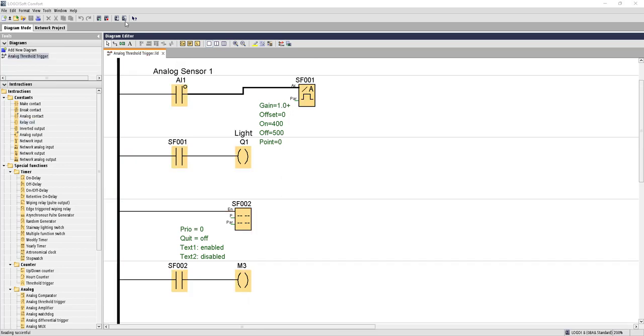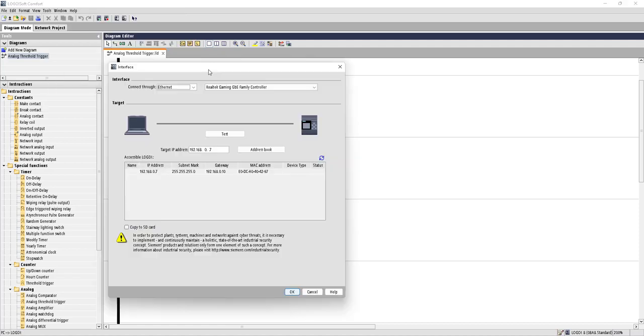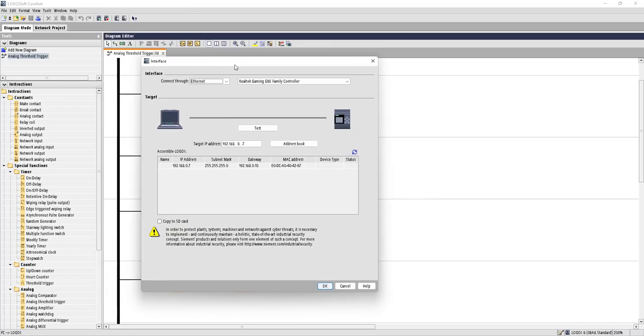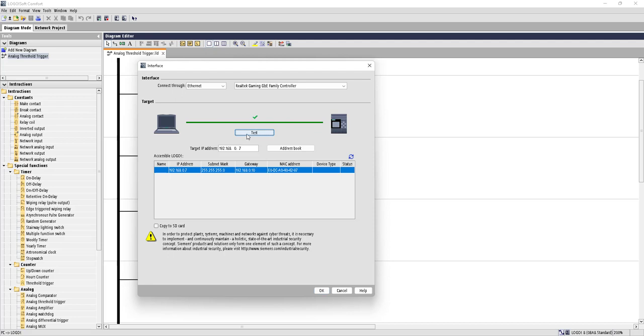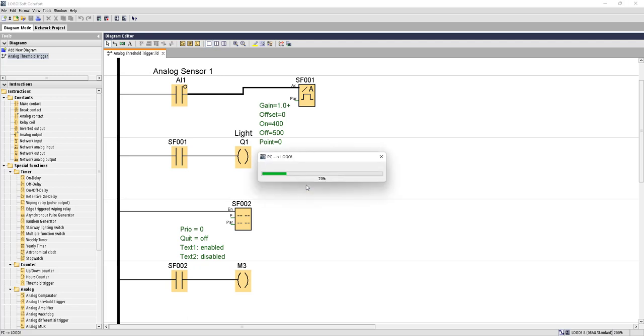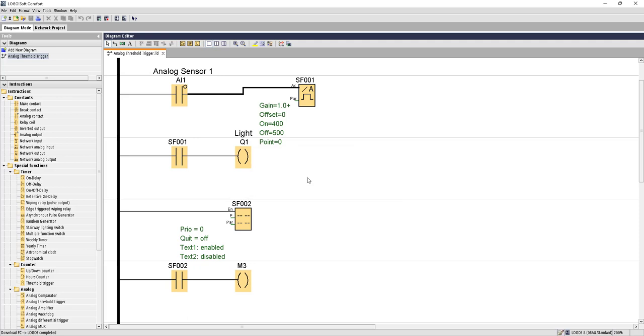The programming has been completed. Now if you want to upload that program to our PLC, we will have to go to transfer from tools, go to PC to logo. Once this window comes up, you will need to put your network addresses for the PLC device. You can also do the testing. Once the test gives you a green tick, you can go ahead and press this OK button. It will start the uploading procedure. Now the program has been uploaded. Do you want to run it again? Yes.